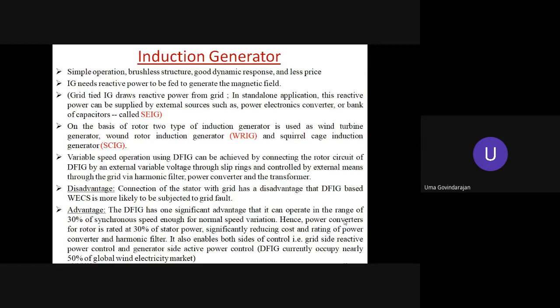self-excited induction generator. On the basis of the rotor, two types of induction generator are used as wind turbine generators. One is the wound rotor, another one is the squirrel cage. Each one has its own advantages and disadvantages, and the research scope is grid integration issues and the fault ride-through capability of induction generators tied to the grid. That's a thing one has to focus on for IG based wind energy conversion systems.